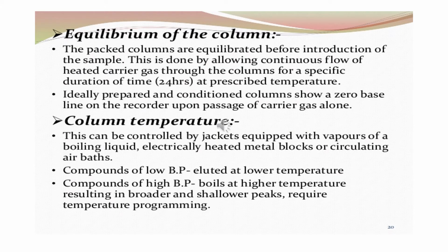Equilibrium of the column. The packed column is equilibrated before introduction of the sample. This is done by allowing continuous flow of heated carrier gas through the column for a specific duration of time, 24 hours, at a prescribed temperature. An ideally prepared and conditioned column shows a zero baseline on the recorder upon passage of carrier gas alone.